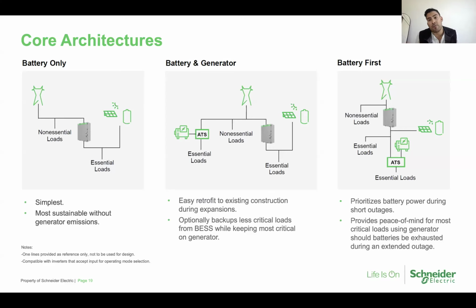It's a great approach. And then to the right, we have our battery first scenario where you have your energy storage system connected to your main switchboard. In this scenario, you can run a battery first where essentially Source Pack acts as a primary service disconnect. So when you lose power, the ATS downstream of that main switchboard will remain connected to source one. What I mean by that is when you lose power, your energy storage system will come online as the primary emergency power source, and the ATS will stay connected to source one. So they'll see a momentary outage, but the ATS will stay connected. That way you can deplete your battery energy storage system first before kicking on to generator. Essentially like an N+1 system. Again, a greener, more sustainable emergency backup power option.